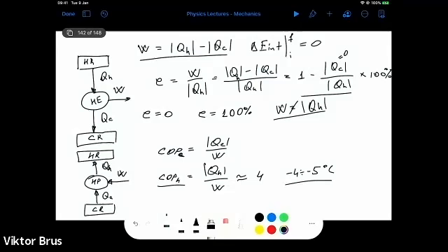So if the temperature drops outside, then of course the COP also drops. And that's why it's not commonly used in areas where the temperature outside drops to low values like -15, -20, and lower degrees Celsius.